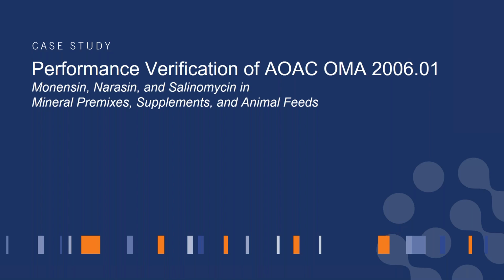You should base acceptance criteria on the current validation studies. Document and describe the transfer or verification process in a plan or protocol. Investigate the deviations from the protocol and document comparative outcome in the transfer or verification report. Next slide, please.